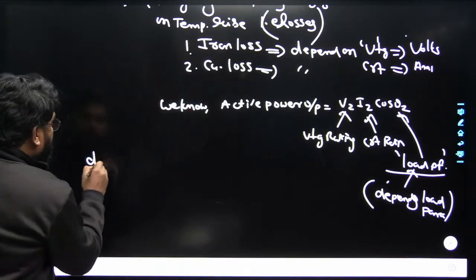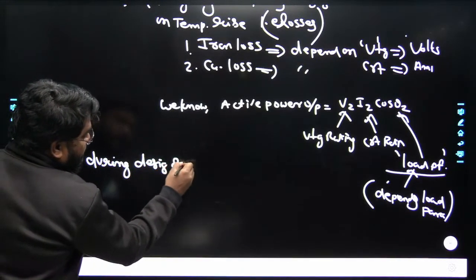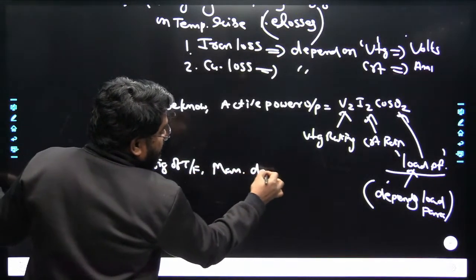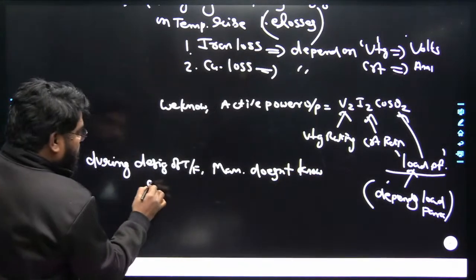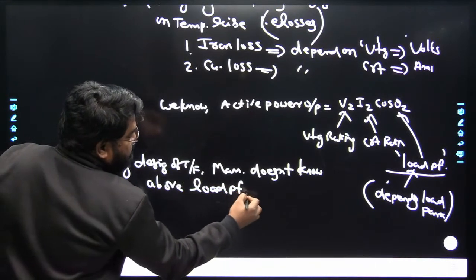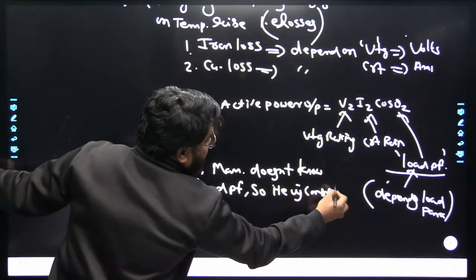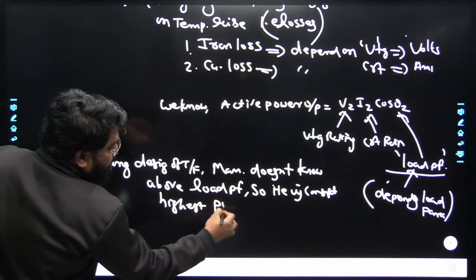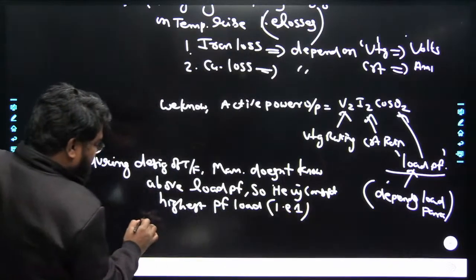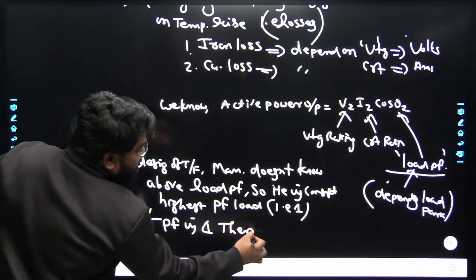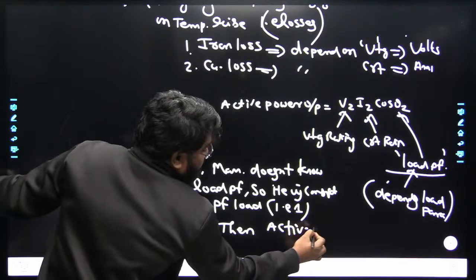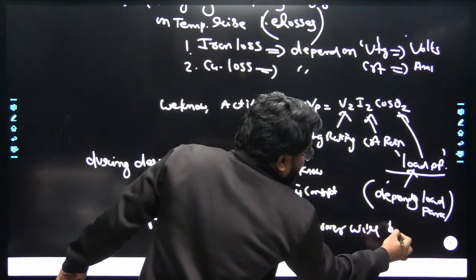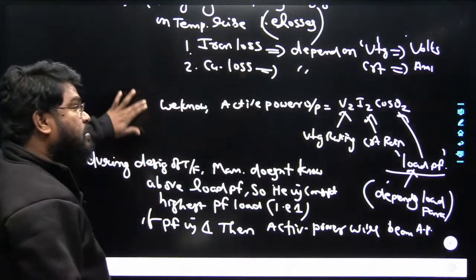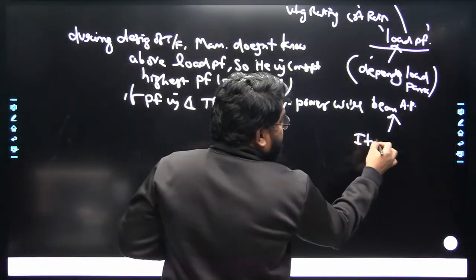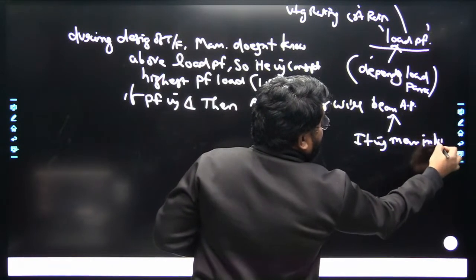So during the design of the transformer, the manufacturer doesn't know the load power factor, so they consider the highest power factor of the load, which is 1. If power factor is 1, then active power becomes apparent power, which is measured in kVA or volt-amperes, kilovolt-amperes or megavolt-amperes. This is the reason why transformer rating is measured in kVA instead of kilowatts.